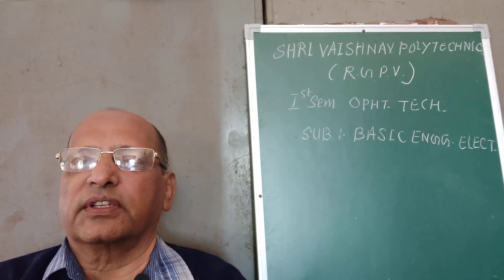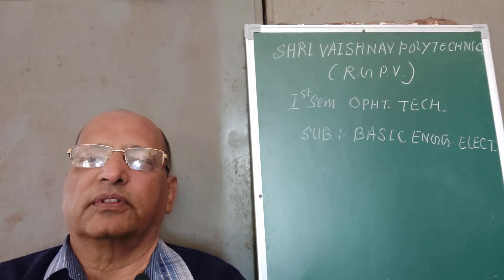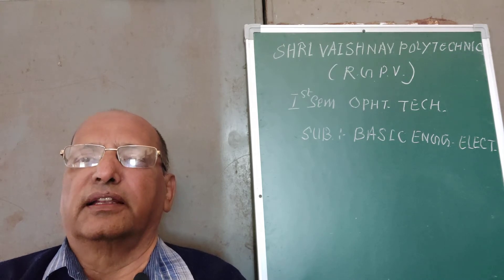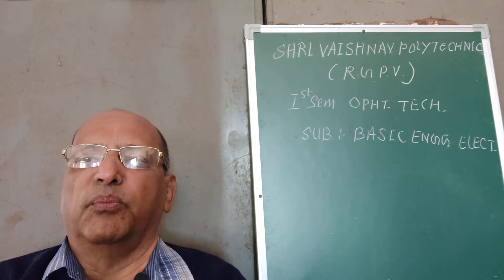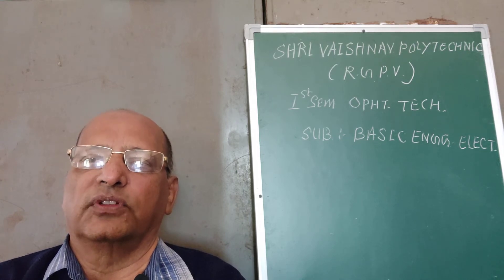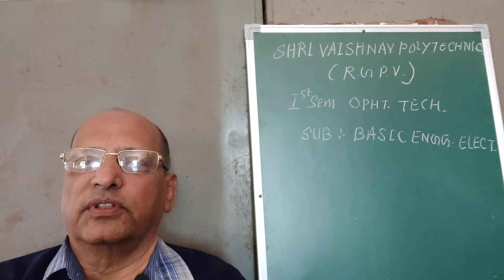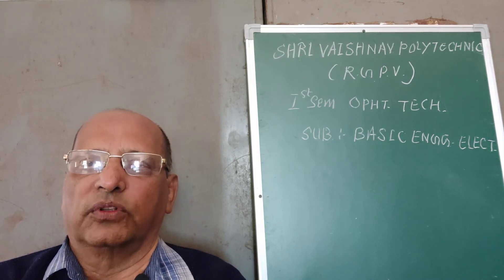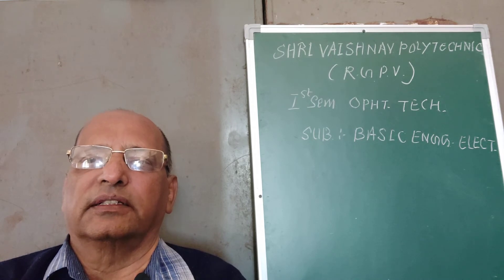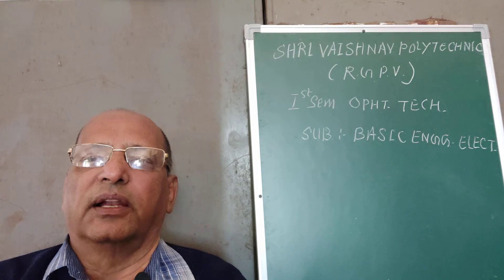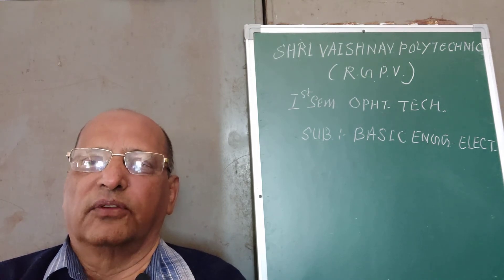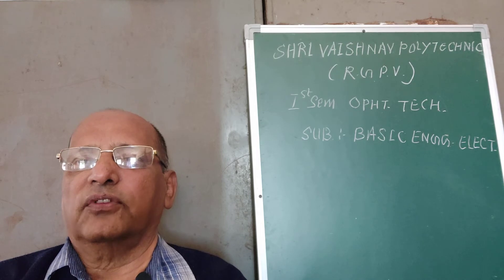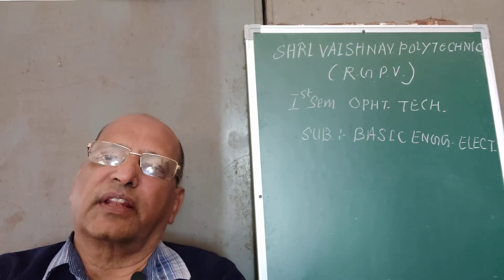The electrical specification in an ophthalmic technology workshop is normally 230 volt, single phase, 50 Hz supply. The rated ampere rating for the main supply is 16 ampere with an ICTP switch. ICTP means iron clad triple pole switch; for single phase it will be an ICDP, that is iron clad double pole switch. Maximum current rating may vary from 16 to 32 ampere, with voltage of 230 volt for single phase and 440 volt for three phase.